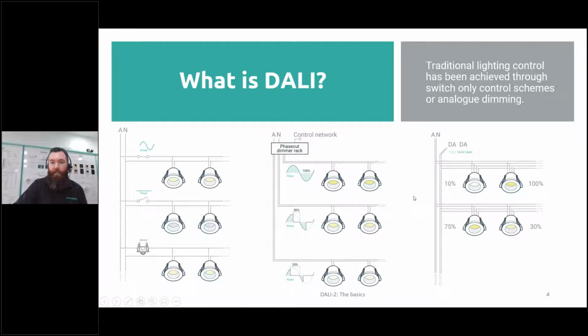So with a DALI line, you have a single line, which can be connected either in a daisy chain, a star topology, basically any sort of format that suits your building, and you can address those independently. So within that same loop or line, you could actually have the light levels of every single device at a different level. When you set up your control schemes for your building, you can configure certain switches, certain sensors to address, to talk to just some of those lights.